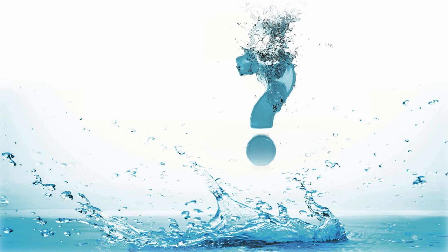But in the thermal desalination techniques, yes, they actually do design specific apparatus to try and avoid adhesion of silica. Now, there are ways that we could potentially take some of that and use cross-flow velocities, for example, to try and minimise that sort of interaction. The problem is that from a mechanical point of view, there are certain types of scale we'd be able to avoid, but there would be other types that we would still suffer from. Things like monomer adsorption processes, which is another major cause, are still going to happen even if we manage to find a way to stop our colloidal attack. We still have that monomeric problem.